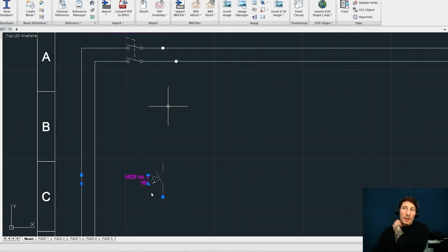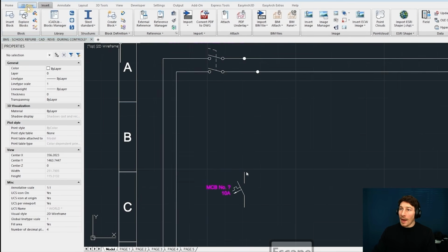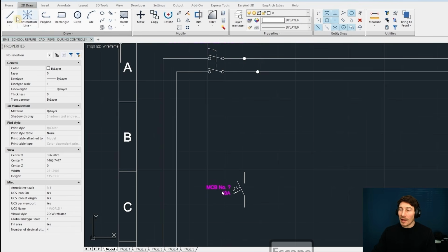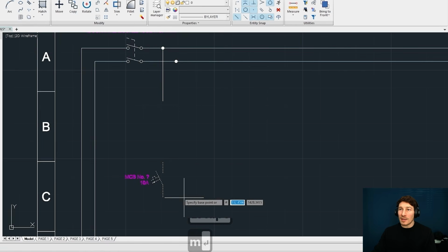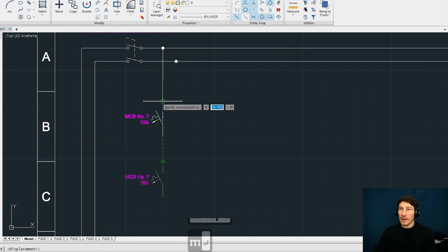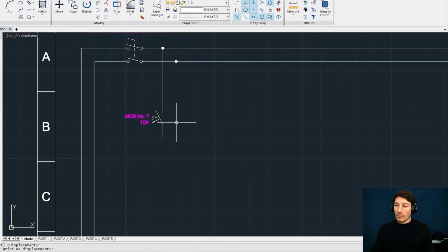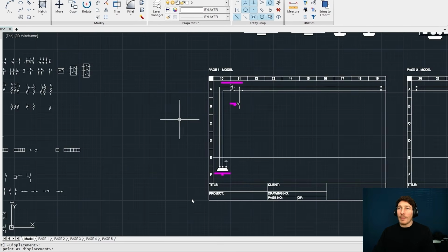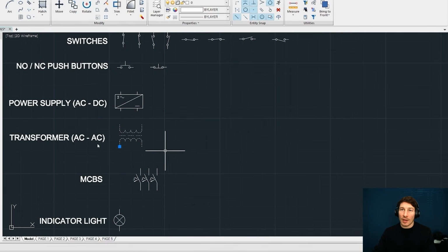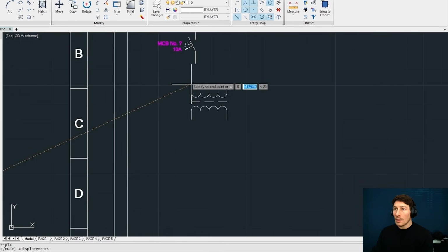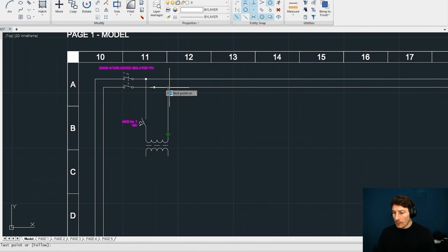and then we've got this live being distributed across these MCBs. And what we're doing here is we're now building or designing that first MCB, which is going to be for the main power supply, the 24 volt AC power supply, as we can see here. So transformer AC, that is the symbol for that. Bring up the images again.